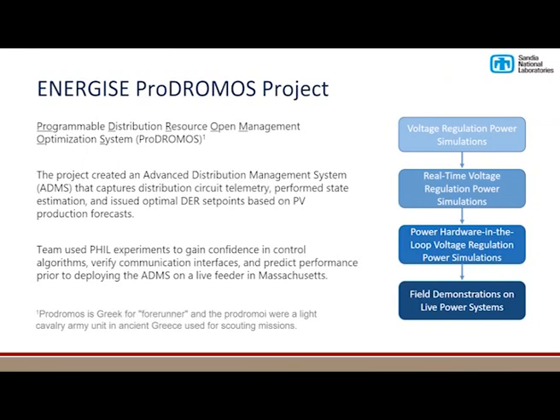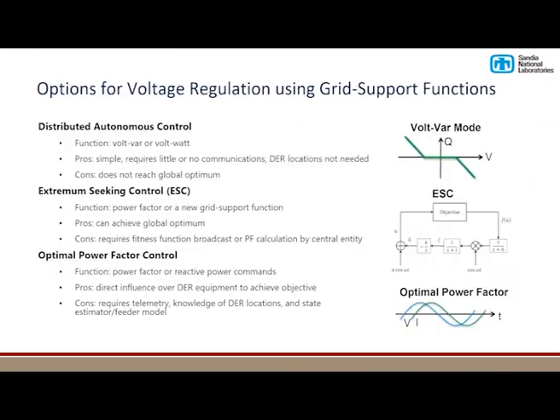By adding more and more fidelity to the operations, the three different grid support voltage regulation techniques that we used, which use different grid support functions, were distributed autonomous control, which is the volt-VAR function in our case; a technique called extremum seeking control, where you inject a reactive power ripple by multiple DER devices and optimize a global objective function based on that ripple; and then a more traditional optimization approach where we use the state estimator to calculate the optimal power factor set points for the devices.